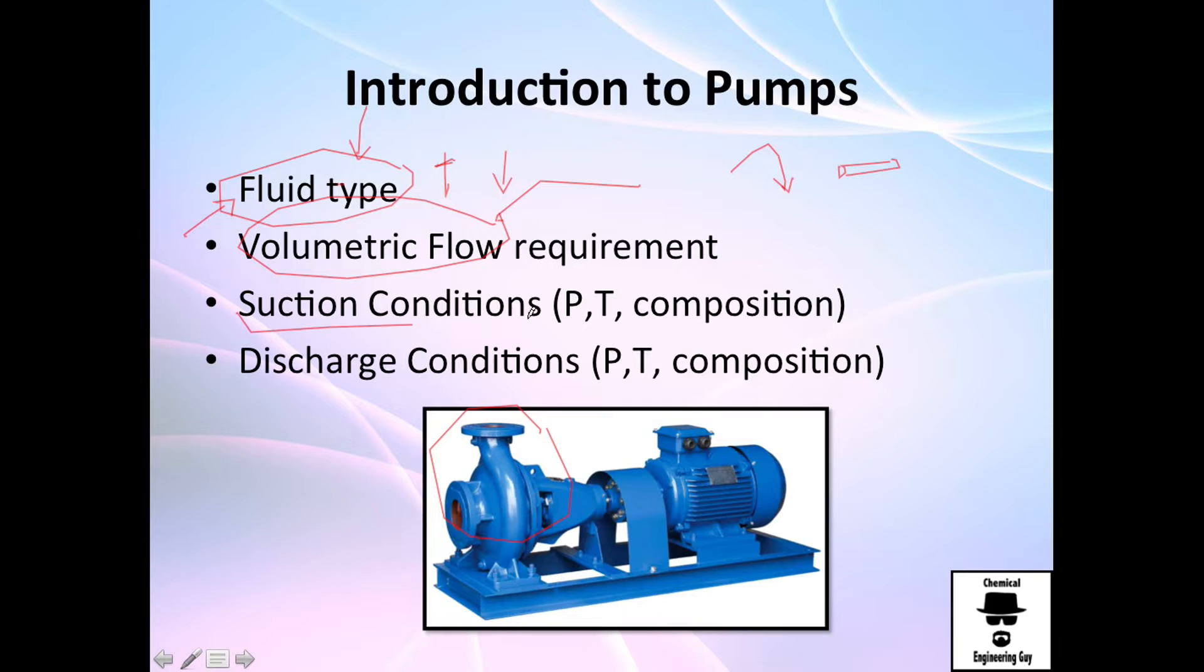You need to know definitely the suction conditions, which is pressure, temperature. Because we might have a very low pressure and therefore you will not be able to operate it. Because when you get this into the eye of the pump, it's going to evaporate and will cavitate your pump. Composition as well.